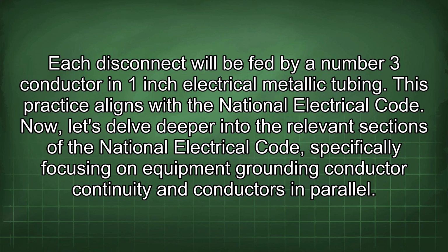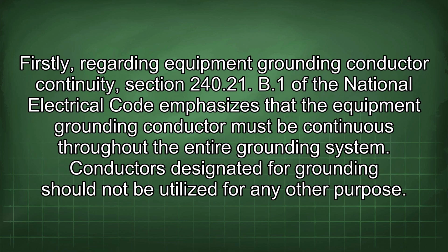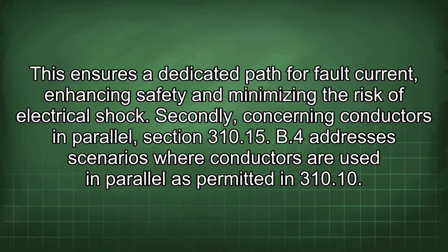Now let's delve deeper into the relevant sections of the National Electrical Code, specifically focusing on equipment grounding, conductor continuity, and conductors in parallel. Firstly, regarding equipment grounding, conductor continuity, Section 240.21.B1 of the National Electrical Code emphasizes that the equipment grounding conductor must be continuous throughout the entire grounding system. Conductors designated for grounding should not be utilized for any other purpose. This ensures a dedicated path for fault current, enhancing safety and minimizing the risk of electrical shock.